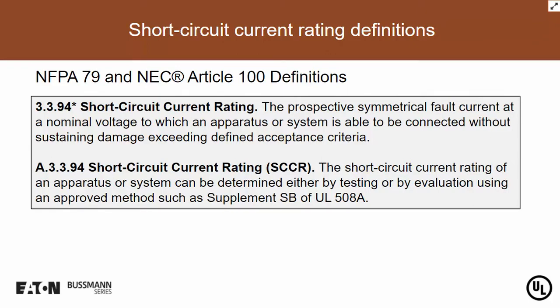When we talk about sustaining damage, the determination whether unacceptable damage has occurred can only be determined by doing short circuit testing. And then, of course, when we talk about acceptance criteria, basically we're referring to the requirements that are in a product standard that defines what is acceptable damage under short circuit conditions for that particular product. There are many, many products that have short circuit current ratings, and of course the level of acceptable damage can obviously vary considerably depending on the type of product. Obviously, when you're doing short circuit testing with fuses or breakers, virtually no damage can occur because those active devices are there to protect equipment downstream, and their job is to adequately interrupt the short circuit current.